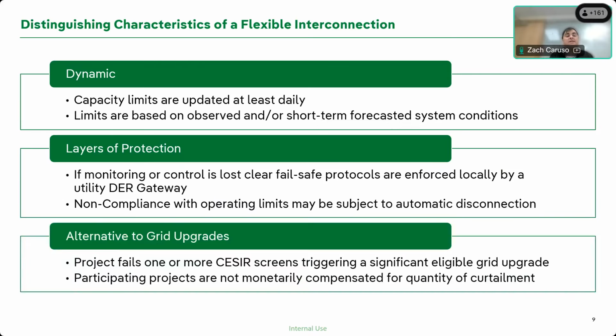And as I said, it's dynamic. It has layers of protection. And the key point is that it's an alternative to grid upgrades, right? Under that firm interconnection scenario, the only way to go over that firm limit is to upgrade the thermal capacity of that transformer bank, to go from that 10.5 MVA limit to a 14 or to a 22. That's the only way that I can put more DG capacity there, because according to our planning constraints, to be able to accommodate them at any time under all kinds of operational conditions, that's what we need. We need a bigger bank to stay within those operating limits.